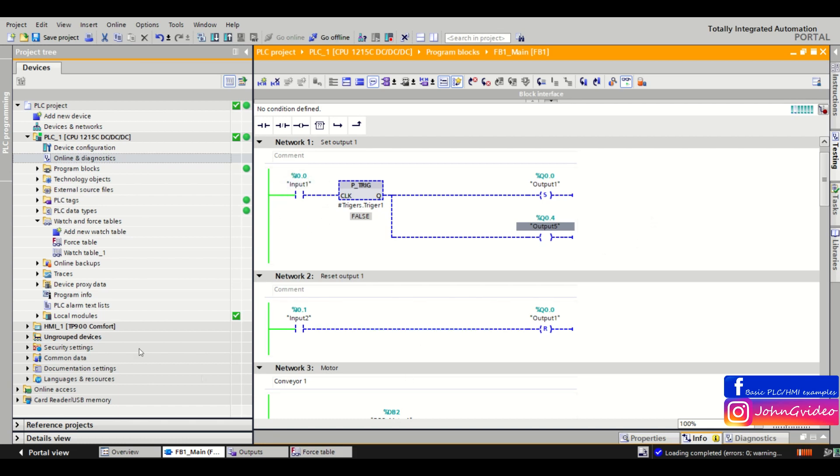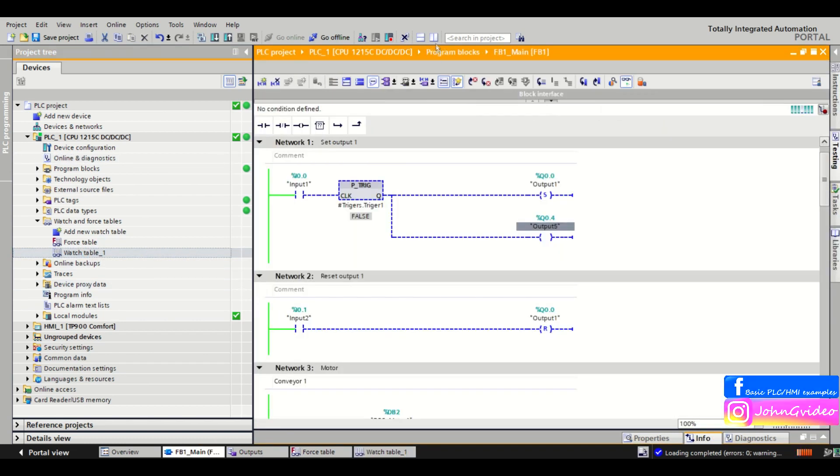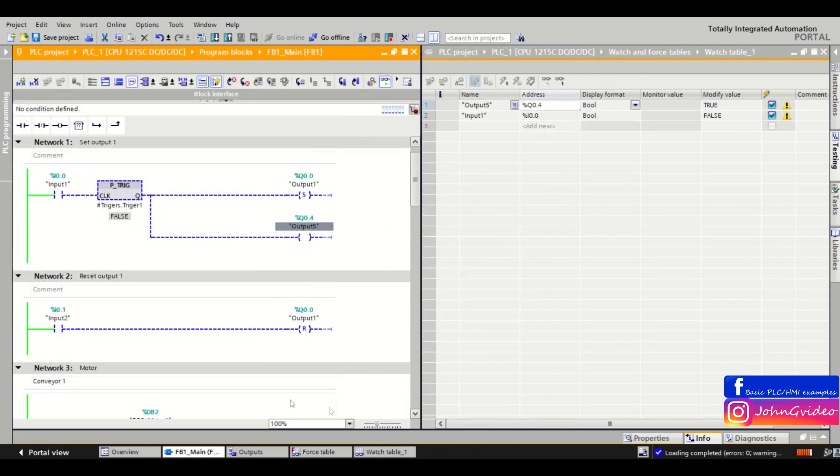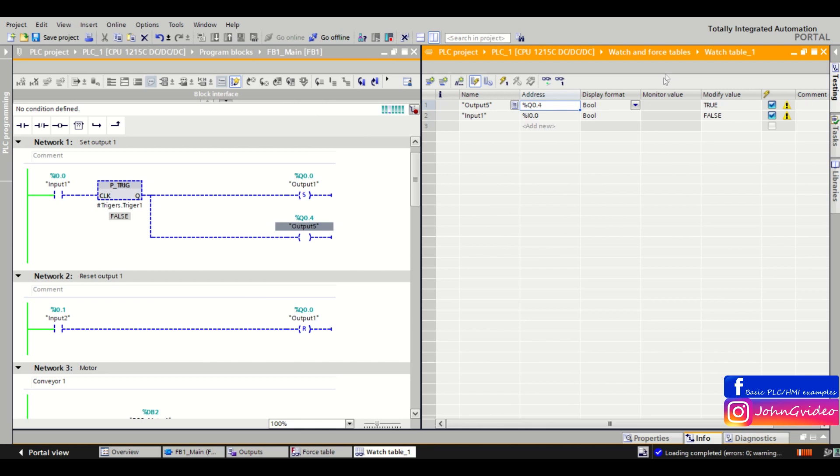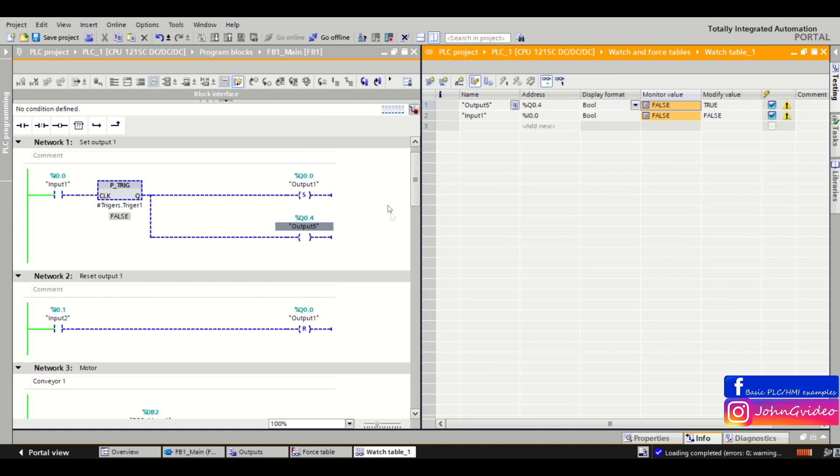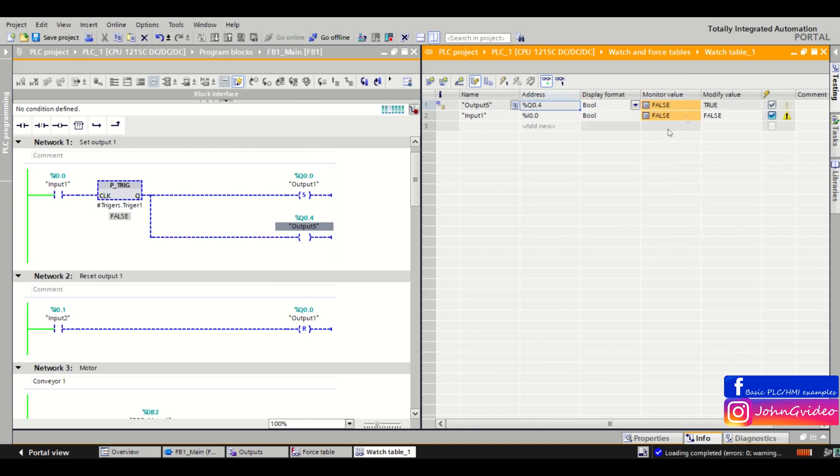Normally when you use the watch table you can't set this output to true because the watch table respects the logic of the PLC program. As you can see it's not true. It's still false because output 5 is true only in the moment of positive edge of the input number 1.